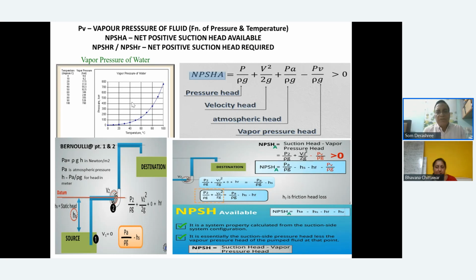So the same pump was running okay, but let's say you have a plant which was in Chennai, and now you're shifting that plant, because of some concessions that the government has given, to maybe Himachal Pradesh. Then you find that this pump has suddenly started cavitating, or there is a lot of vibration and noise, and it is not pumping properly. Everything was okay when it was in Chennai, but not here. So you have to take care of this. That's why you must understand this one very important characteristic: vapor pressure, not only of water, but of any fluid that you are pumping.